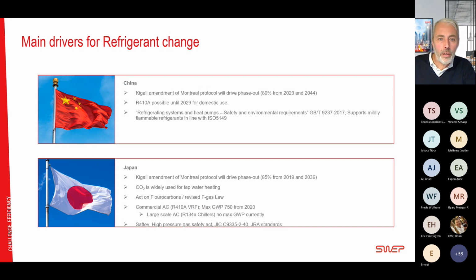Some drivers for China. China has ratified the Kigali Amendment, and it's a total phase out of 80%, starting in 2029 and continuing until 2044. We expect 410A to be used domestically until 2029, when the phase down is initiated. Their safety standard for refrigeration systems and heat pumps is denominated GB/T 9237-2017. It supports mildly flammable refrigerants, and it's actually very similar to ISO 5149.